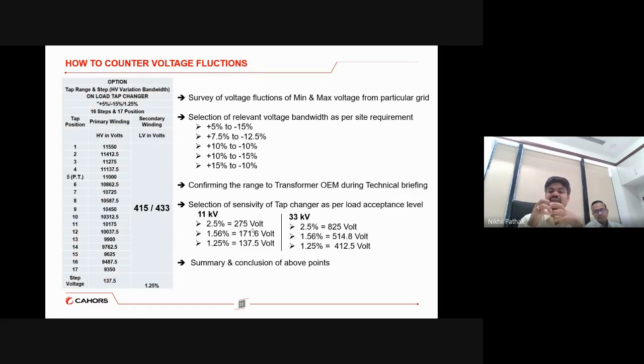So the customer has to define their comfort and the minimum requirement. If they are okay with 2.5% and fewer operations in the OLTC tap, and better consistency and balance between the fluctuations and the number of operations, they can go for 2.5% also. So I'm just giving an example. This has to be done, and the summary and conclusion have to be defined before approving the drawings and confirming the requirement to the OEM, so that the OEM can give an appropriate design instead of giving their own ready designs with a low delivery time and just delivering the product in time, and then on site it will make an issue. That kind of situation we can really avoid in such cases.